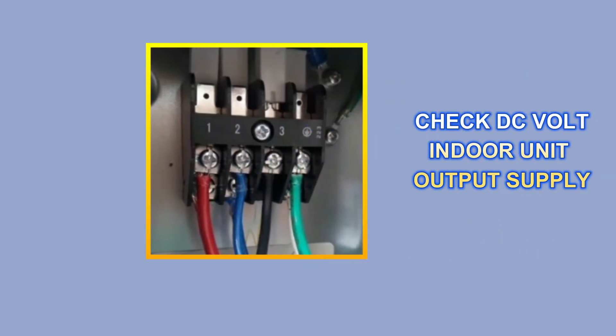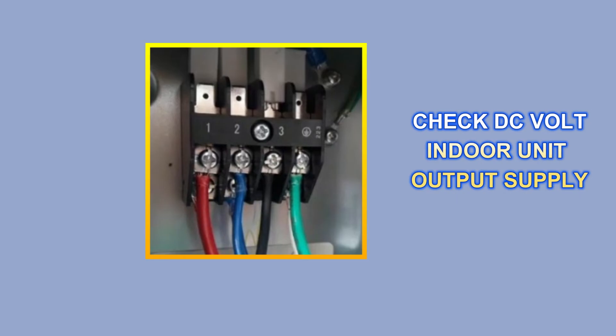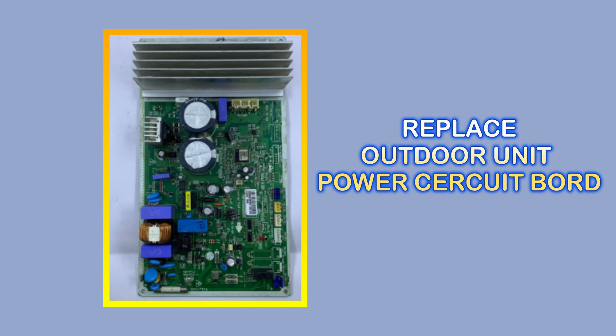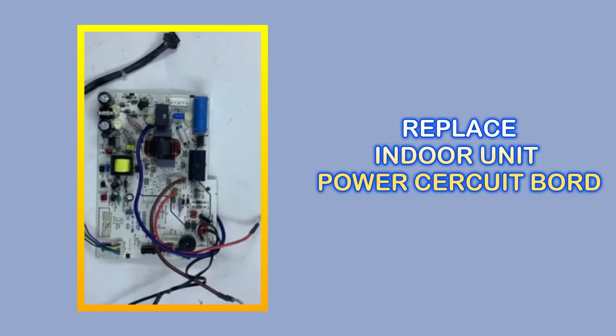If the same color code wire is installed and the error is still coming, then another reason could be: first, turn on the indoor unit and open the wiring cover of the outdoor unit. Now check the DC voltage at the output supply of the indoor unit. If the indoor unit is providing DC output supply and you are still getting this error, then you will have to replace the PCB of the outdoor unit. If the indoor unit is not providing output supply, then you have to replace the power circuit board of the indoor unit. After that, this error will be completely fixed.